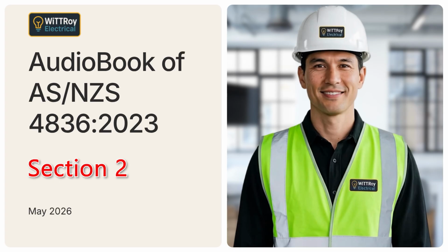Clause 2.3.5 explains hazardous areas. Hazardous areas can create a risk of fire or explosion. These areas may contain flammable gas, vapor, or combustible dust. Live work must not be carried out within hazardous areas. Sources of ignition must be carefully controlled.